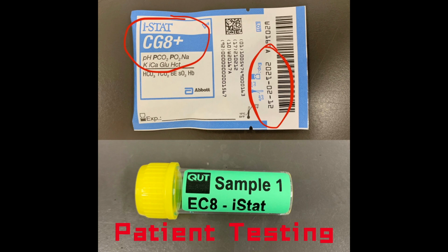The cartridges are usually sealed in individual pouches and are refrigerated at a temperature between 2 to 8 degrees. Make sure to place the cartridges in room temperature for at least 5 minutes prior to testing. If the pouch has been punctured, the cartridge should not be used. Furthermore, you should also check the expiry date and make sure the appropriate type of cartridge is used. Now we will start our demonstration.